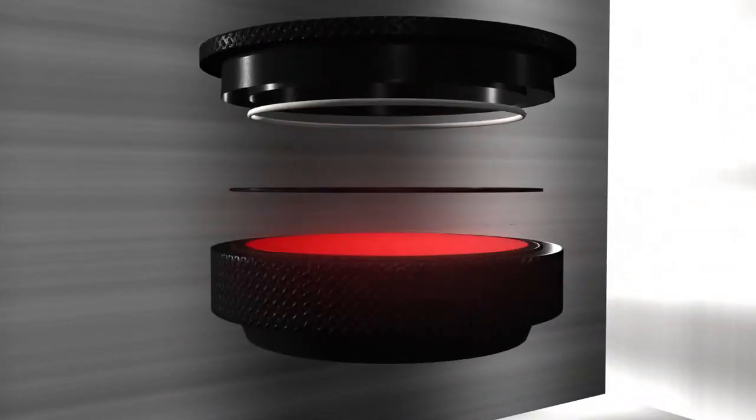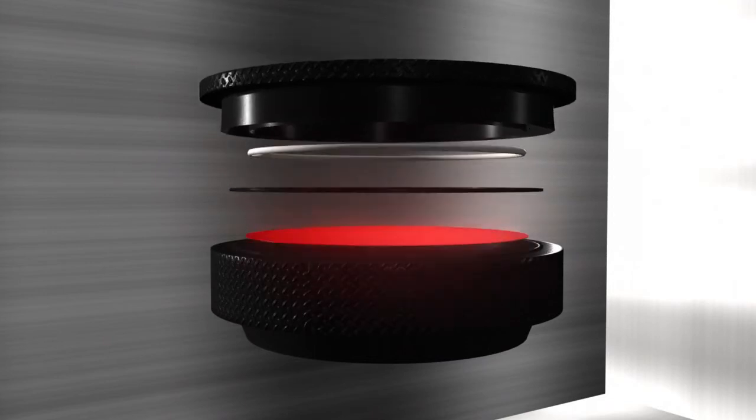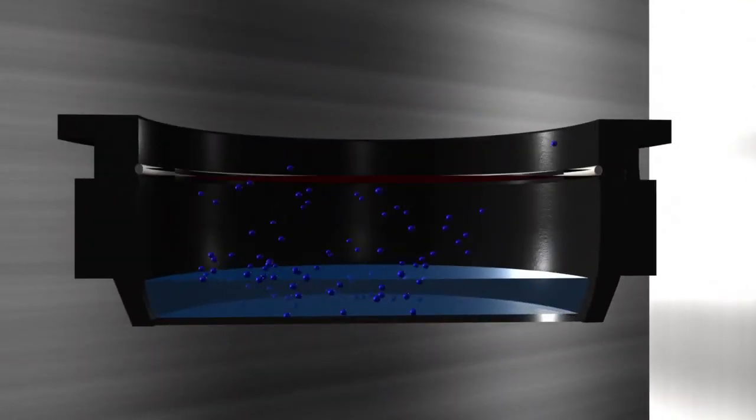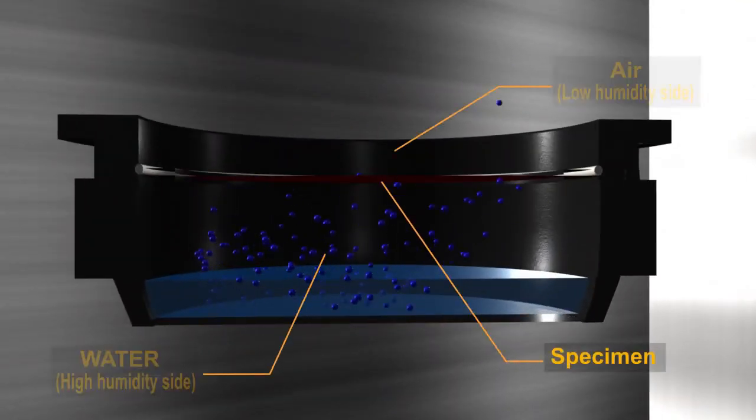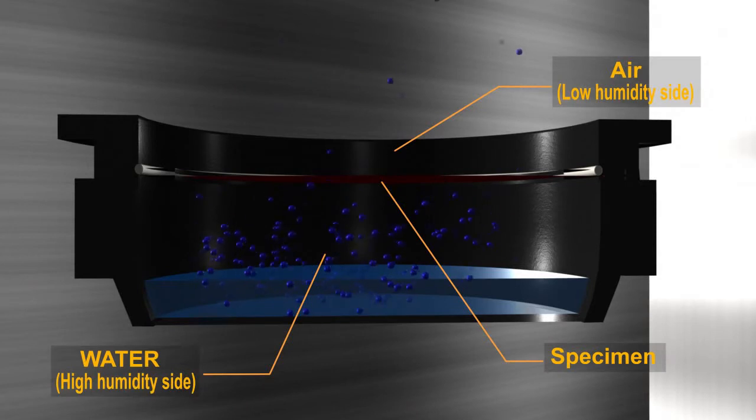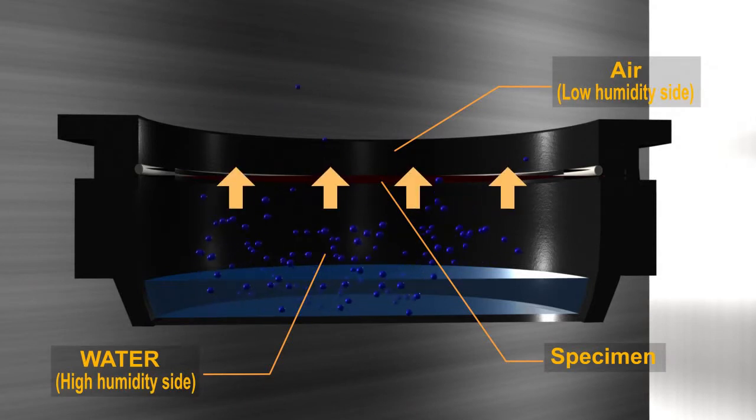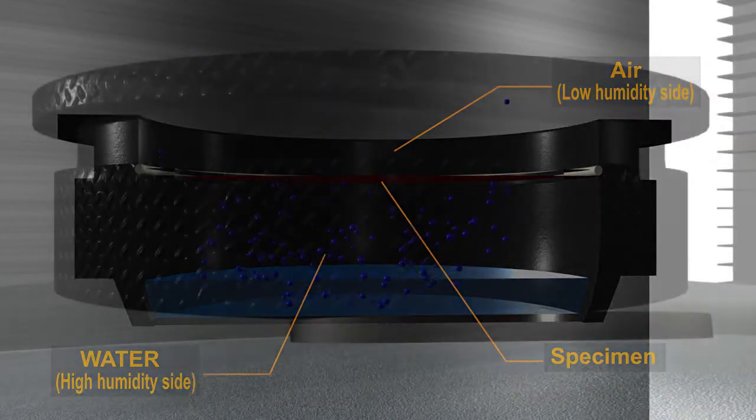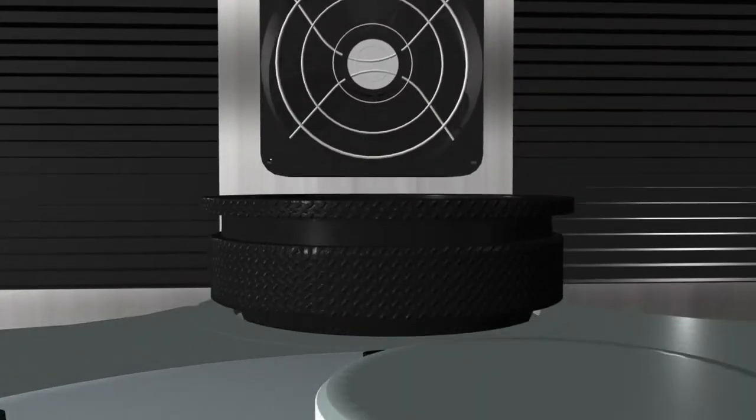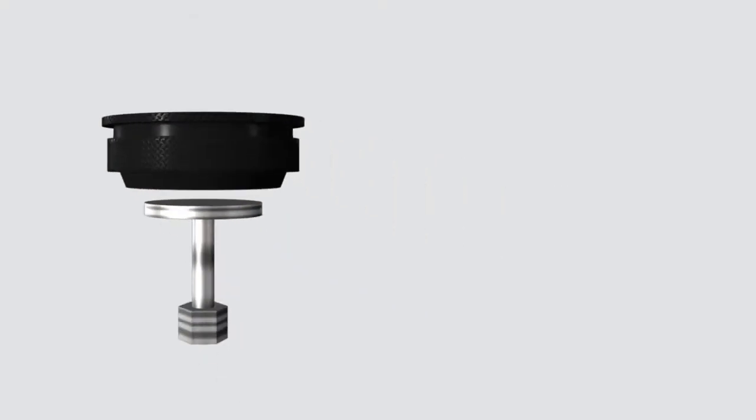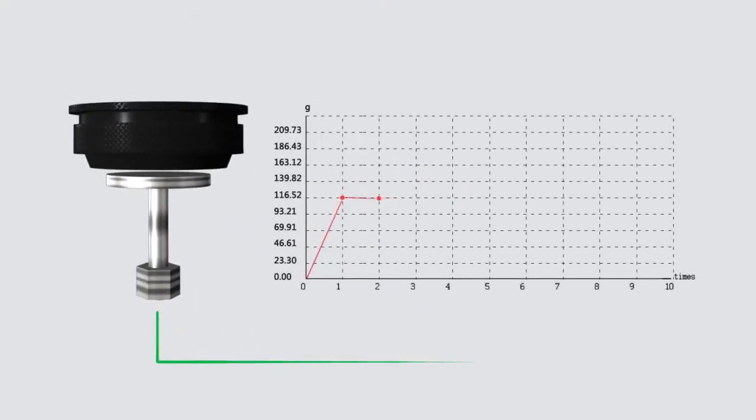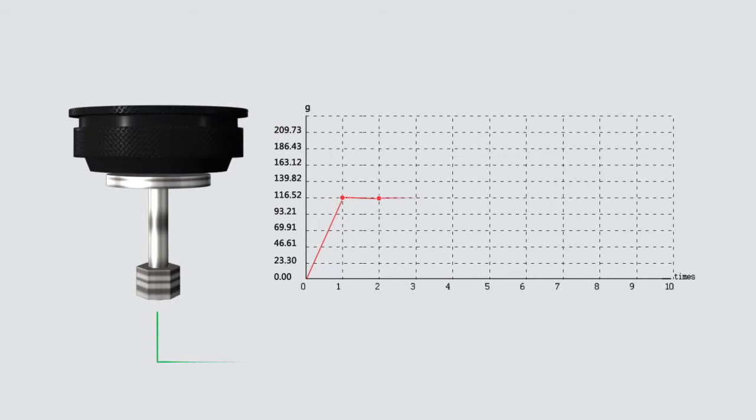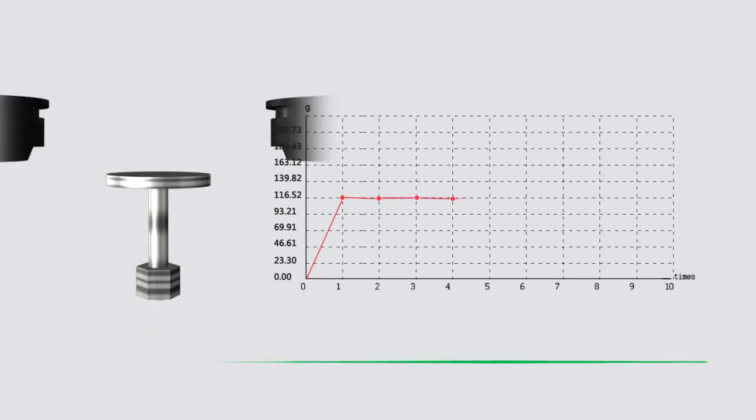W3060 works by firstly establishing a specific humidity difference across the specimen. The water vapor molecules permeate from the high humidity side to the low humidity side. The water vapor transmission rate and other parameters are then obtained by detecting and calculating the weight changes of testing cups through time.